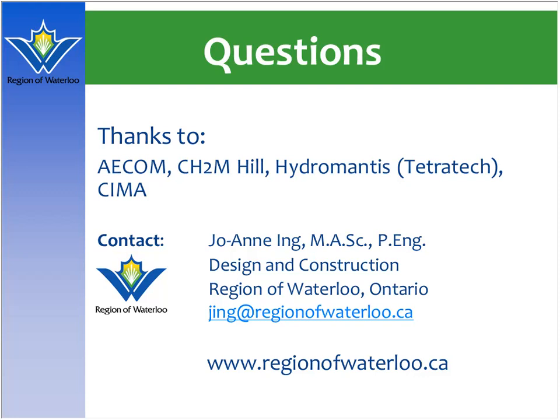Through the wastewater master plan in 2007, it was decided to consider centrifuges to treat the sludge and to stabilize. The other part, too, was the fact that land application was becoming quite difficult because it's only seasonal. We had to consider a 365-day process instead of a seasonal process, which land application can be. So going with treating the biosolids with the centrifuges seemed to be the way to go, because it could be operated all year round. The final disposal that we are doing is at landfills, as well as I think in a mine in northern Ontario. We are actually in the process of a biosolids master plan currently, so we are evaluating further options to look at sludge stabilization and potential nutrient removals.